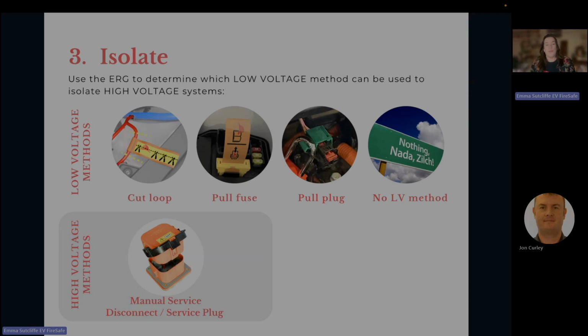Here in Australia we don't typically carry 1,000-volt gloves on trucks. So our advice from EV Firesafe is we're happy to pull or cut loops, pull fuses, pull plugs, but where an emergency response guide directs a responder to a manual service disconnect, if that vehicle's been in a workshop environment, mechanics workshop, yeah, happy days, we can pull that plug with all the right equipment. But by the side of the road, following a collision, it's pissing with rain, you're standing in wet grass, we're not comfortable pulling that manual service disconnect.